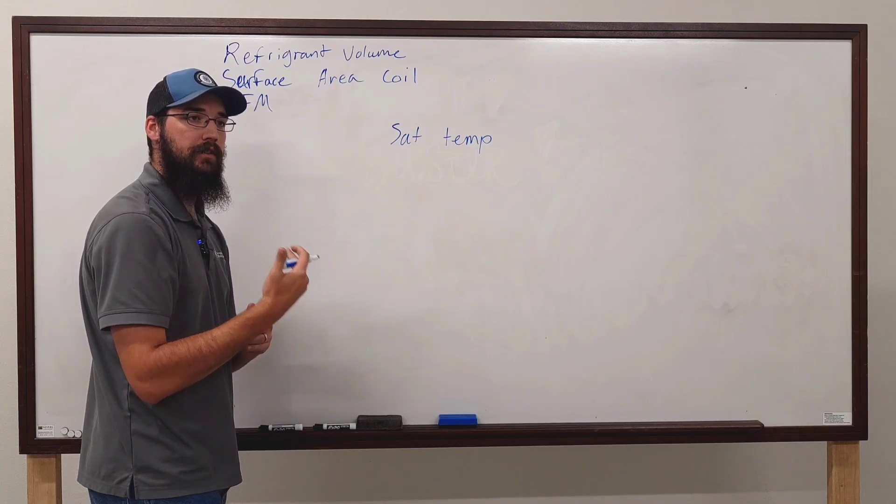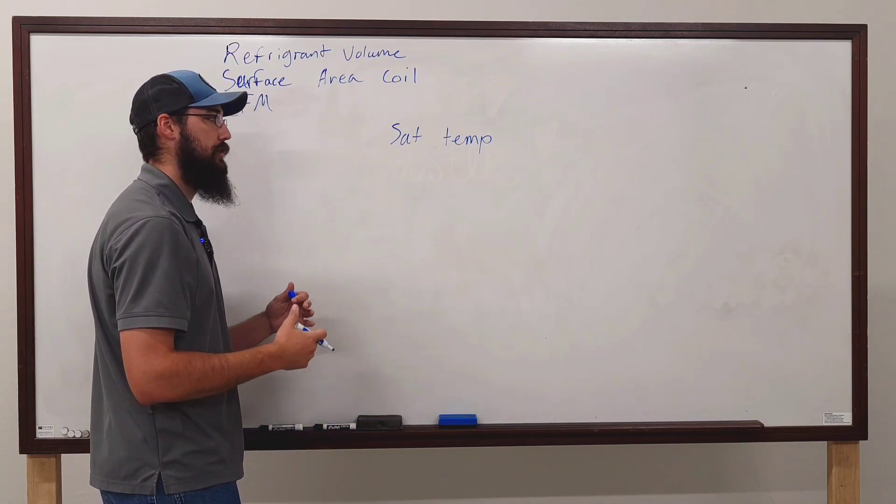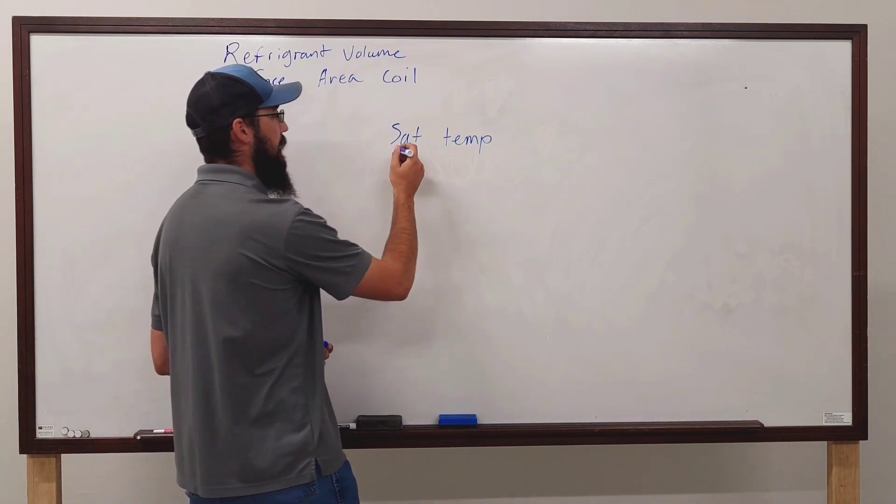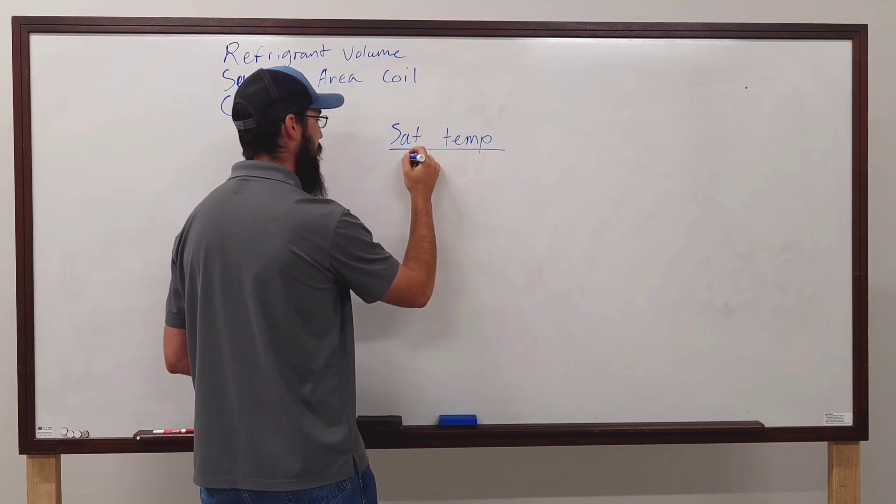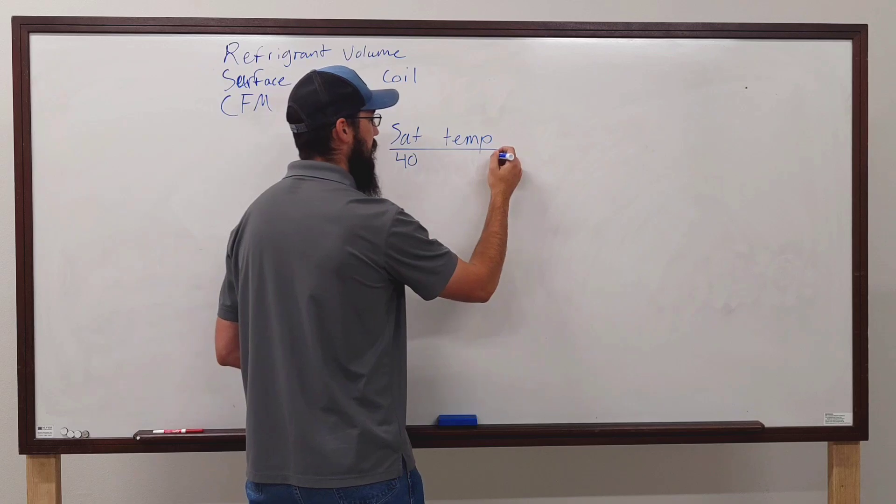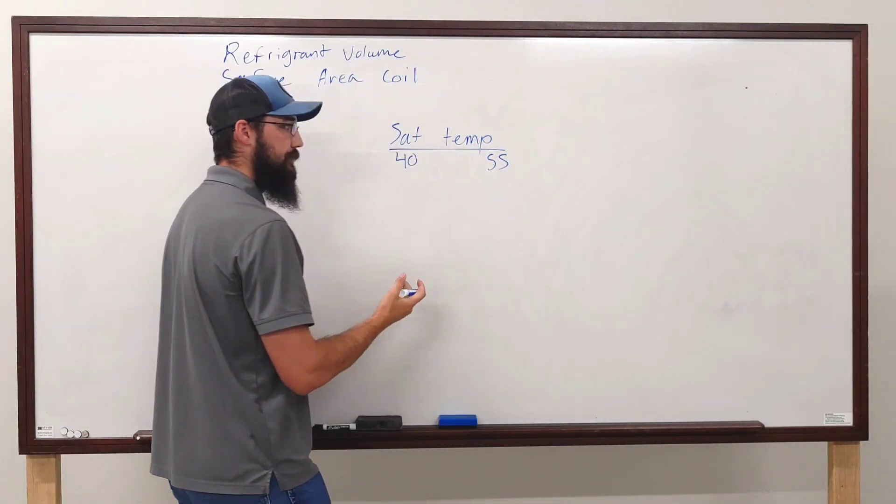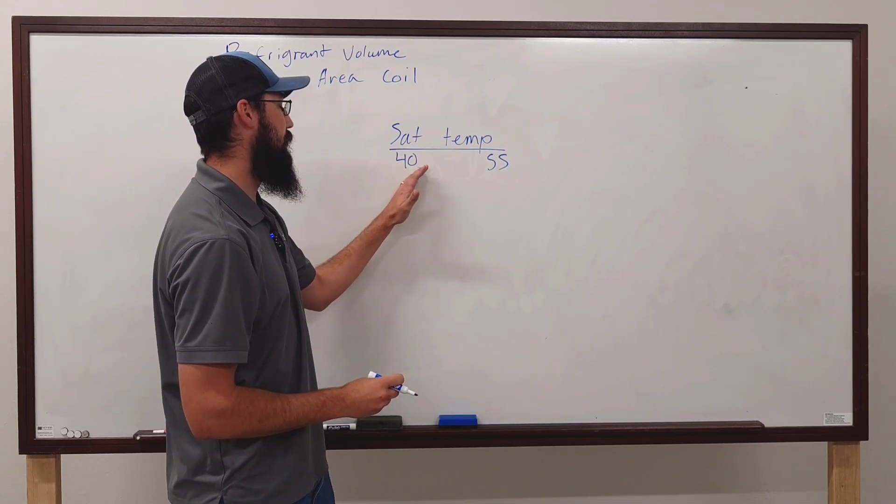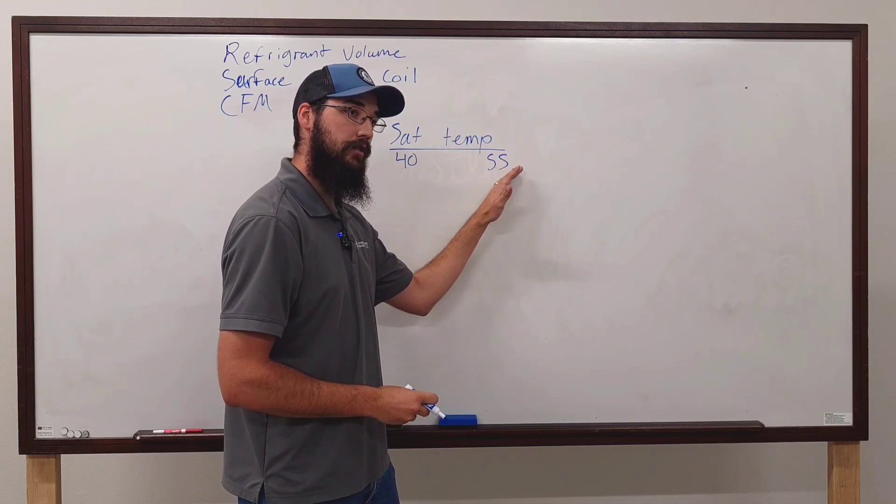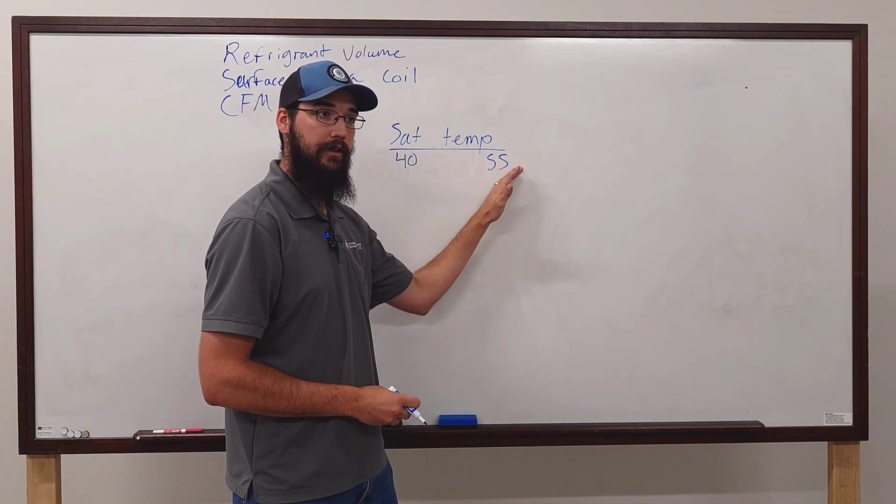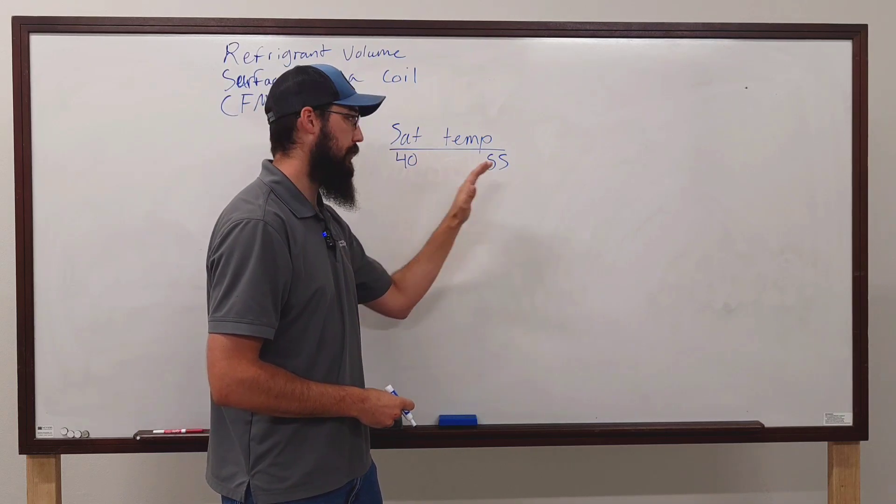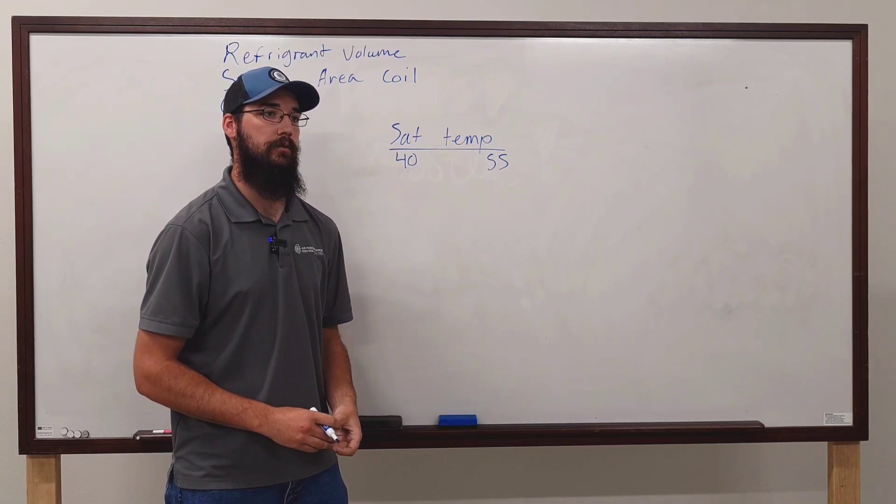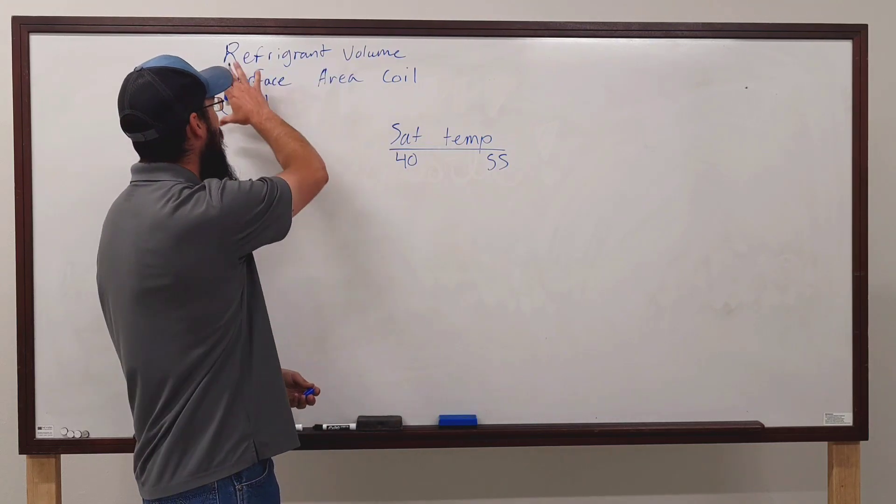Why does that saturation temp matter and how is it affected depending on the coil itself? And this is where we start talking about system efficiencies, whether it's a high efficiency, low efficiency, 13 SEER, 25 SEER, whatever. All of that plays into this number. Whether we're trying to run 40 or 55, which one is it? Which one is correct? Because if you walk up to a system that's trying to operate at 55 degrees of evaporator saturation and you want it to run at 40, and you're thinking something's wrong when there's nothing wrong, it's doing exactly what it's designed to do.